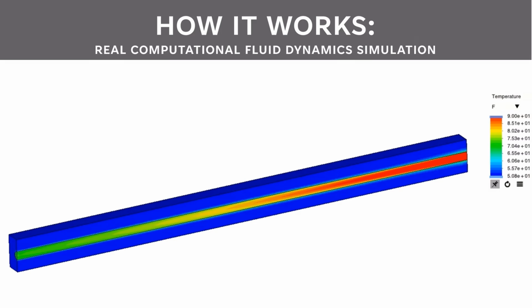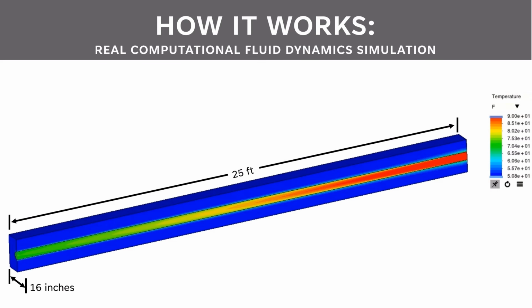Here I've broken down the heat exchanger to a single tube with its surrounding soil. First, we have 16 inches of soil as though we were spacing tubes every 16 inches. I have it sectioned in half for viewing purposes so we can see what's happening inside. The length of the tube and the soil is 25 foot long. The starting soil temperature around the tube is 50 degrees Fahrenheit, which is a realistic temperature to have in the morning just before we start storing heat as the sun comes up.